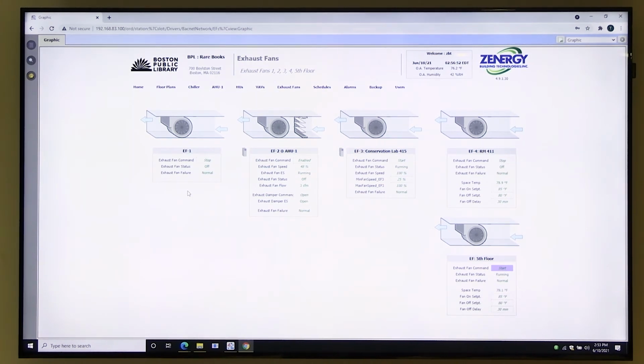Oh, EF1, I'll put a label on there. It's tied to the smoke removal post-purge system. So after an event, God forbid you have a fire or anything, you go to the smoke removal panel and basically EF1 sucks the air out of the system using the same ductwork as the air handler. It's this kind of crazy smoke damper system. There's a post-purge panel in the Fire Command Center. That's what EF1 is for. So basically you'll never see EF1 run ever. EF2 is the air handler.